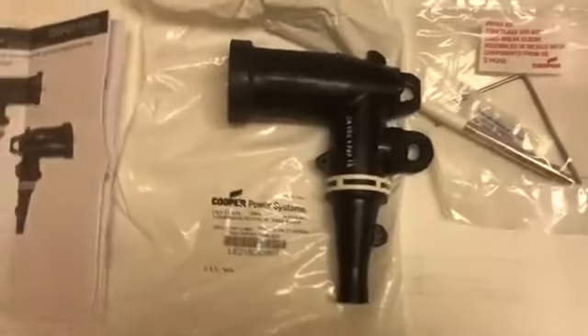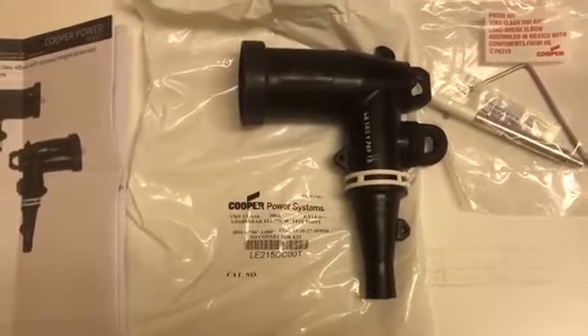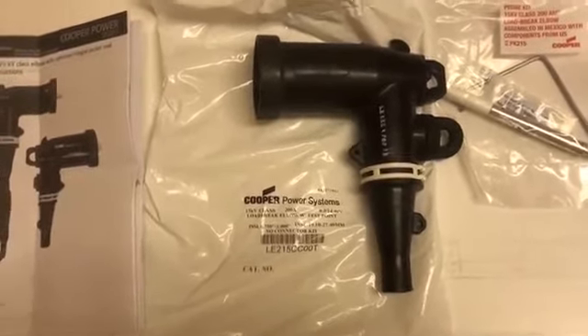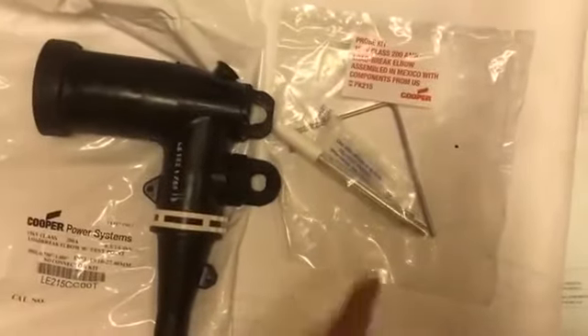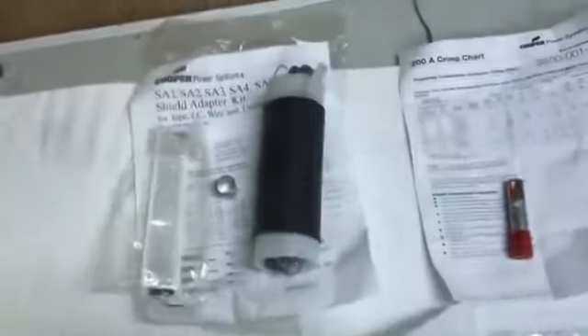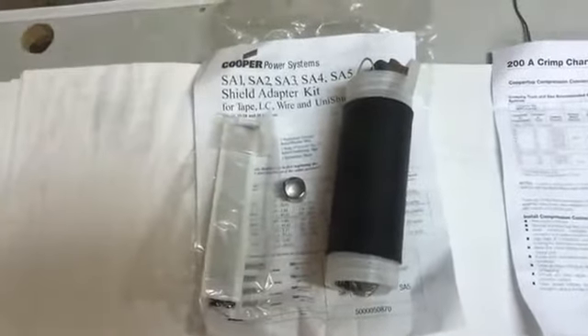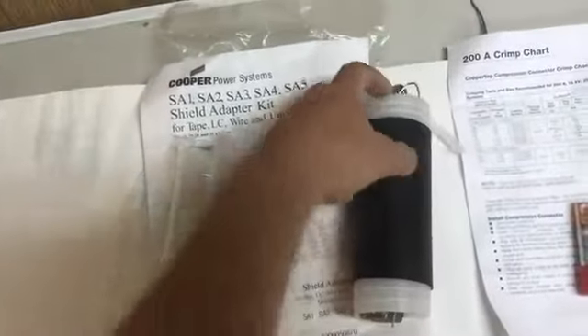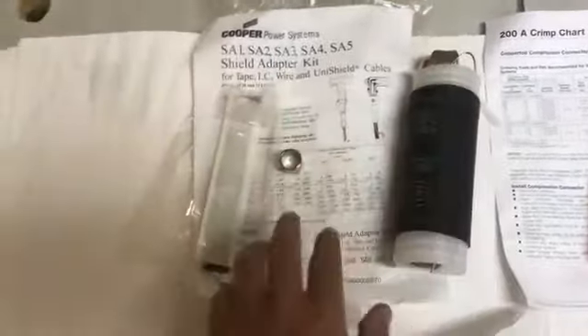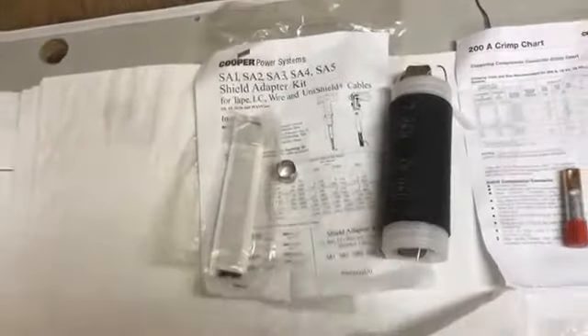Just going over the actual apparatus we're going to be installing today. This is a Cooper 200 amp loadbreak elbow with a capacitive test point. Comes standard with the probe insert tool, and a couple silicone packets. We have a 1-aught copper top with a threaded insert right there. You see it's got the threads in there, and that's actually what the probe itself is going to thread into once it's crimped onto the cable inside of the actual boot. And then we have a Cooper SA2 cold shrink kit with ground braid and drain wire, along with the constant force spring and the mastic that goes along with the SA2 kit.